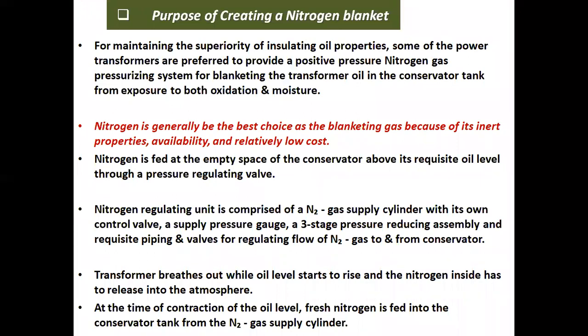Now, the purpose of creating a nitrogen blanket. For maintaining the superiority of insulating oil properties, some power transformers are provided with positive pressure nitrogen gas pressurizing the system, for blanketing the transformer oil in the conservator tank from exposure to both oxidation and moisture. Nitrogen is generally the best choice as the blanketing gas because of its inert properties, availability, and relatively low cost. Nitrogen is fed into the empty space of the conservator above its requisite oil level through a pressure regulating valve.